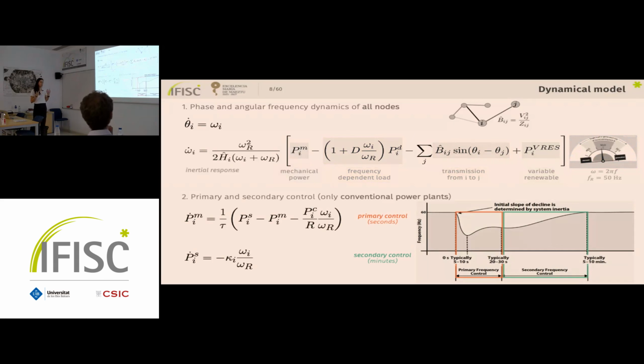When there is a contingency, for instance a lack of generation, the frequency falls below the reference value. That initial decline is determined by the inertia of the system. Primary control kicks in within seconds to stop the frequency from deviating more, and then secondary control restores the frequency back to its nominal value.